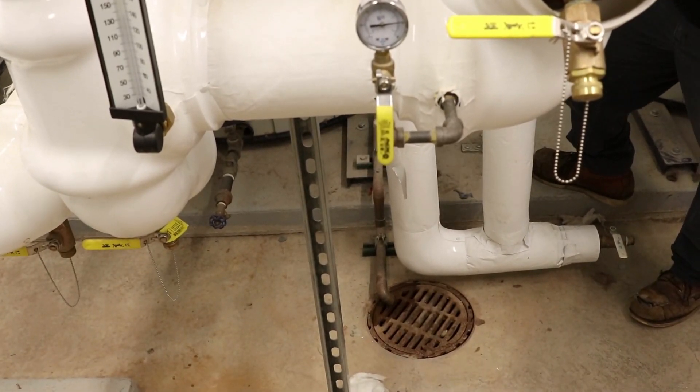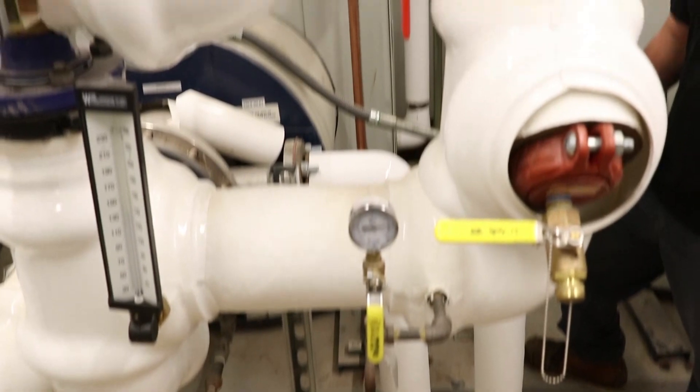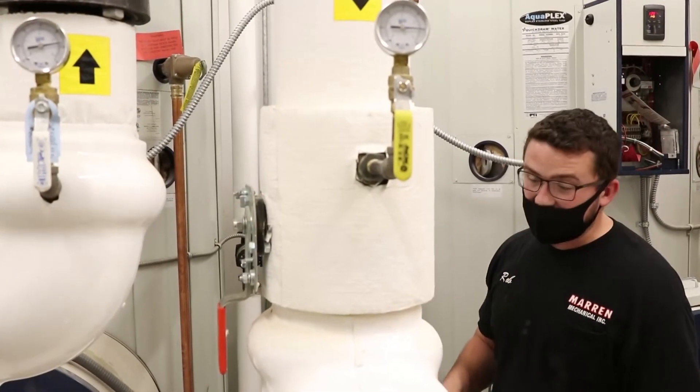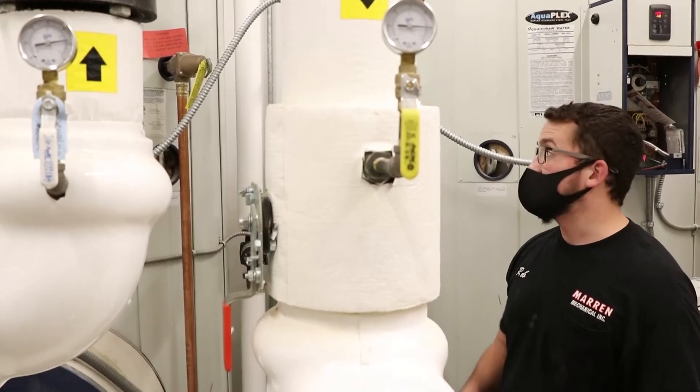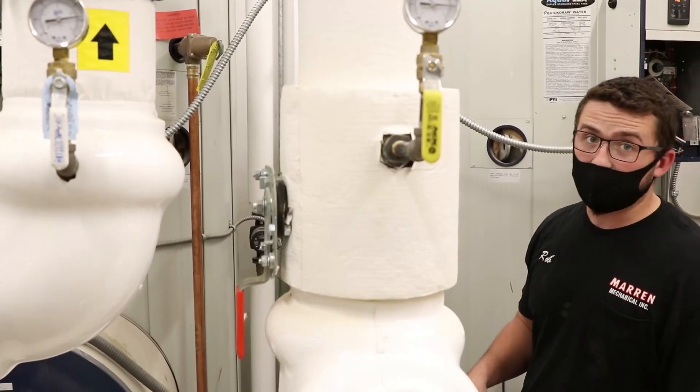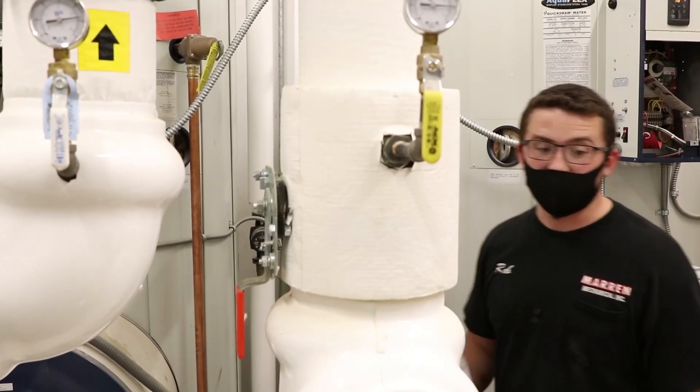If you're not able to get water to discharge out of that drain by lifting the lever, the relief valve needs to be replaced. If the water does not stop coming out of that drain after you let go of the lever, the relief valve needs to be replaced. Either of those instances, you should call for service.